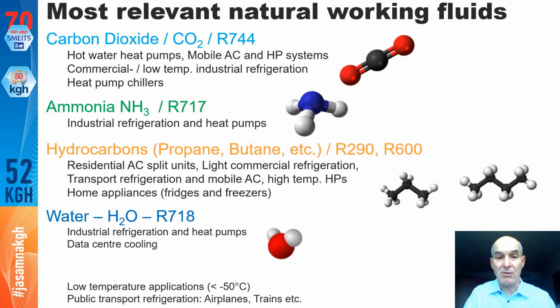Hydrocarbons, we all use them in our residences. Even now you can buy split units with R290. Light commercial applications have deployed hydrocarbons all over the world, in bottle coolers and many shops. Transport refrigeration also utilizes a lot of hydrocarbons, mainly propane. We see some high temperature heat pumps where we can utilize the properties of both butane and propane very well, achieving 120 to 130 degrees C, necessary in some applications where we have to reheat very hot water to sterilize and so on. Home appliances have been transferred to hydrocarbons many years ago.